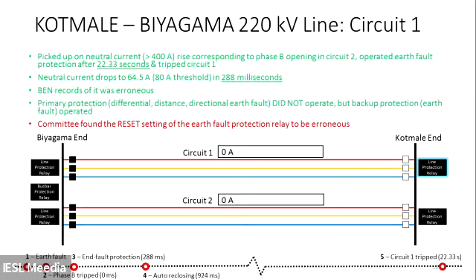Then another incident took place in the other circuit, circuit 1. When phase B went off, the neutral current increased, and that was picked up by earth fault protection. And 22.33 seconds later, circuit 1 also turned off. Nevertheless, in the various waveforms and data provided, after 288 milliseconds the neutral current went down to 64.5, which is below the 80 ampere threshold.